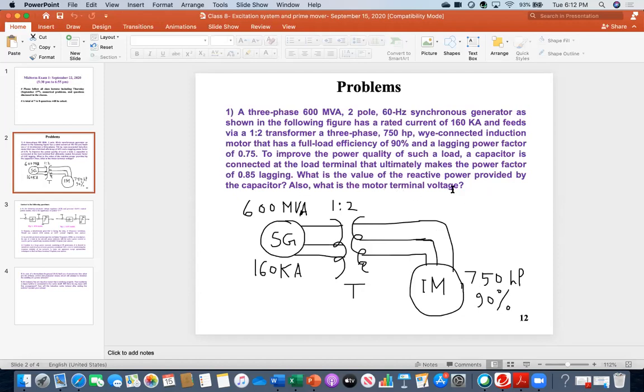So what is the value of reactive power provided by that capacitor? Definitely the capacitor provided reactive power—what is the amount of that reactive power? And also, what should be the motor terminal voltage? What voltage is available here? What is the rated voltage at the motor terminal, the RMS value, line voltage? So there are two questions.